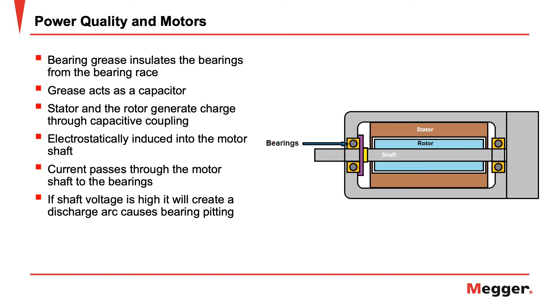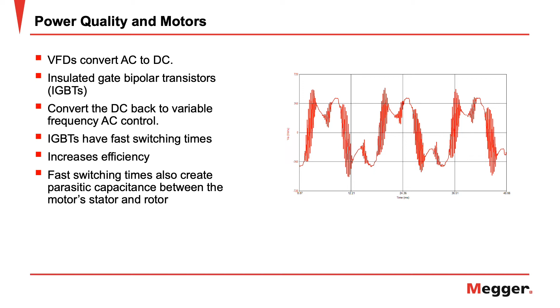VFDs convert AC to DC. Insulated gate bipolar transistors, or IGBTs, are used to convert the DC back to a variable frequency AC control. IGBTs have fast switching times. This reduces energy losses, allowing for higher efficiency. However, these fast switching times create parasitic capacitance between the motor stator and rotor. Winding failures are another common cause of failure, and these can occur due to overheating and/or shorts between coils.